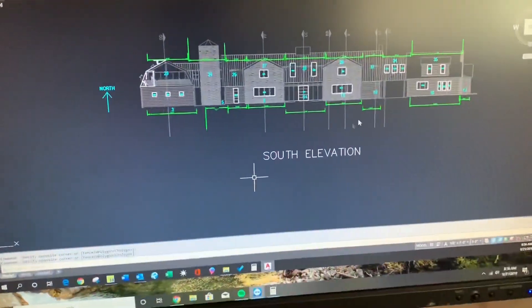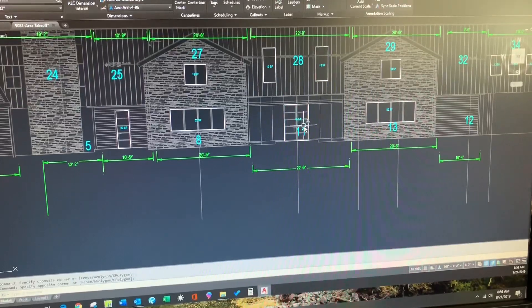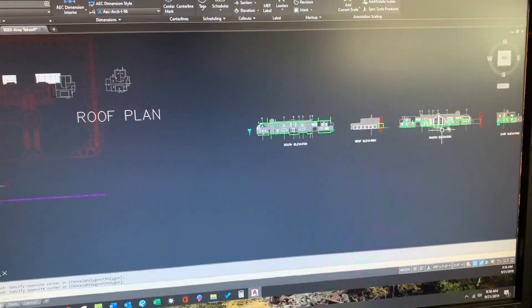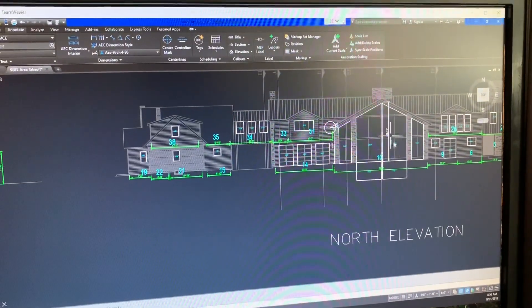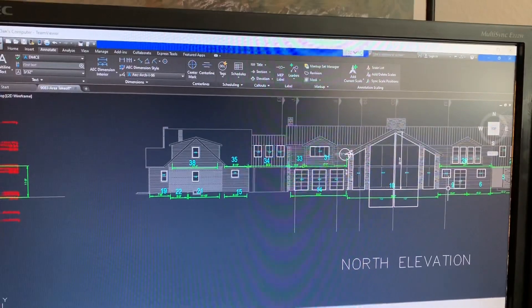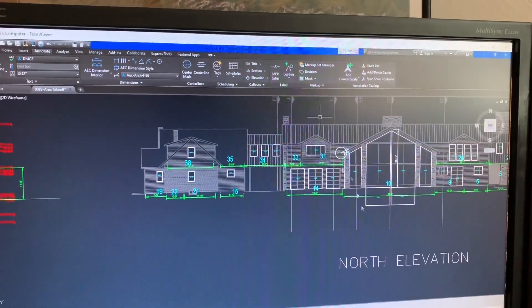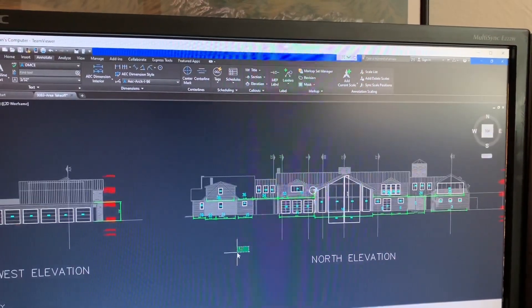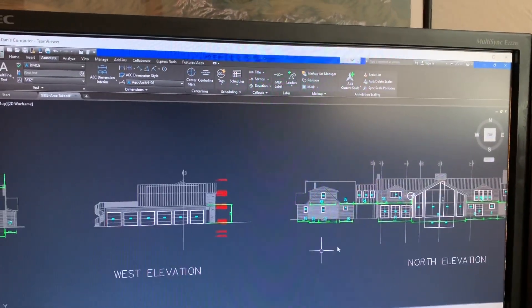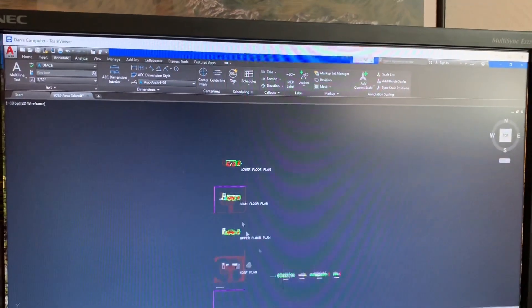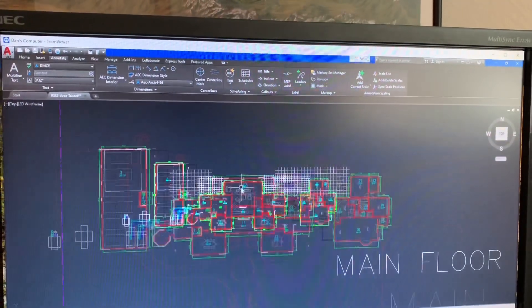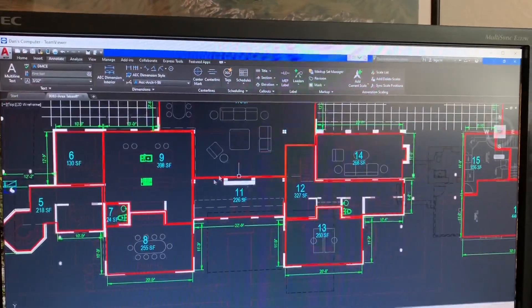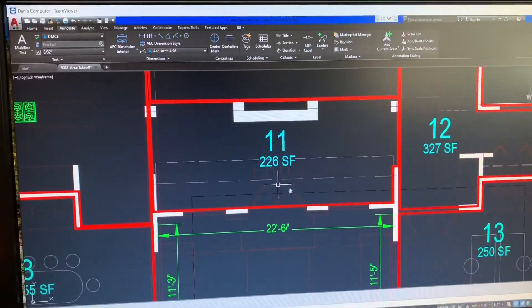Five to six people in the living room and dining rooms. Other than that all the rooms are unoccupied. We're going our way across the front. I'm doing the entry. Just at the great room. These are some big windows here. 562 square feet of glass along that north wall. And I'm looking at zone 11, which is our next number up in the load calc, which is our entry. And you can see the double door swings.